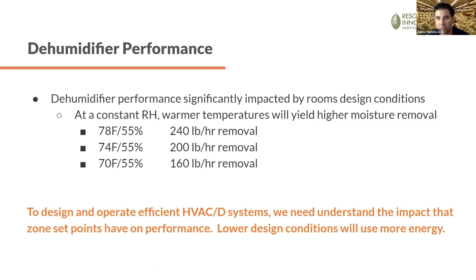We're leaving that constant at 55%, and we're just moving from 78 degrees to 74 to 70, as an example to show the amount of moisture removal. Pounds per hour is how HVAC engineers calculate moisture removal, and that's converted over from gallons per day on a room basis that you would put into that space, less runoff. You're going to calculate how much moisture removal we need on a pound-per-hour basis, and that's how we would size the air conditioning system. So you're effectively almost doubling the capacity of that system in that 8-degree differential.